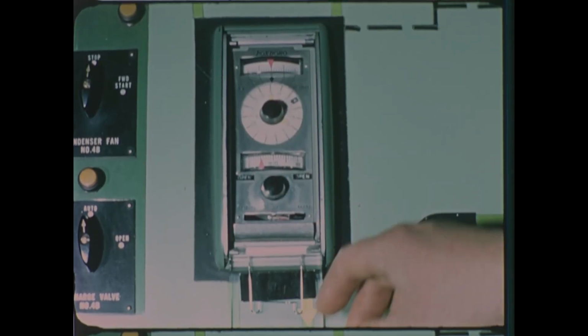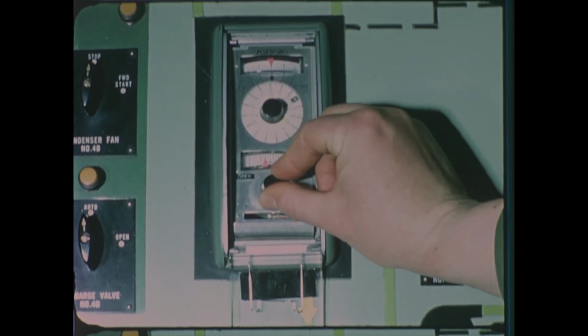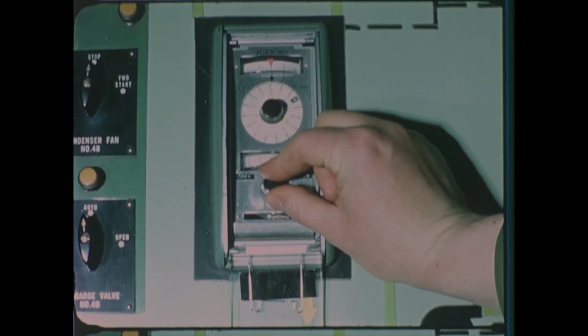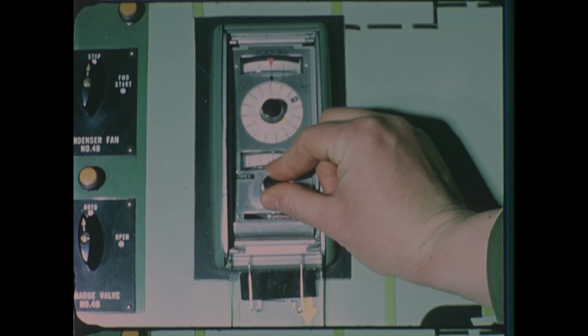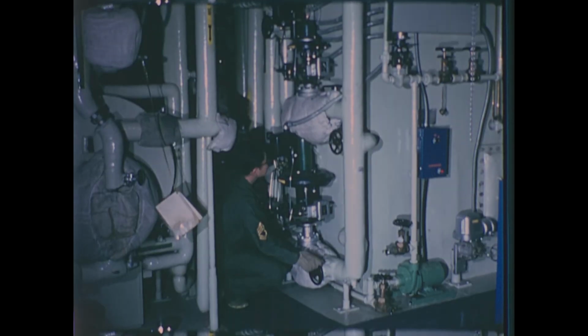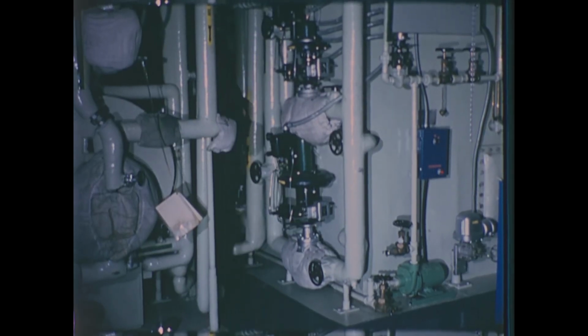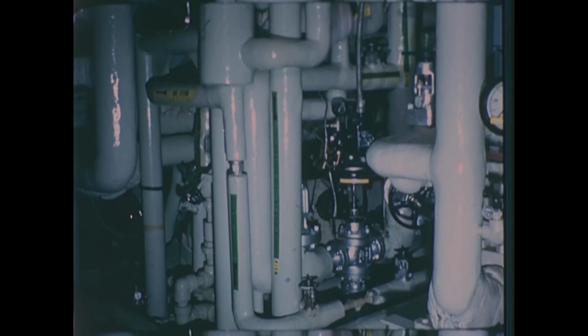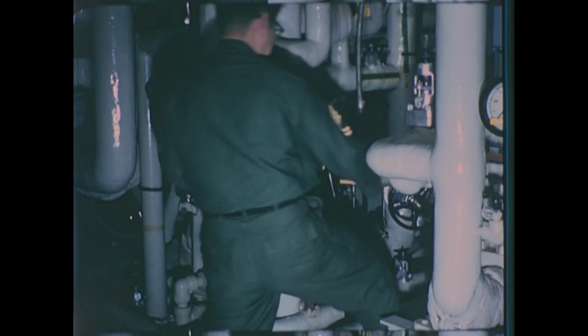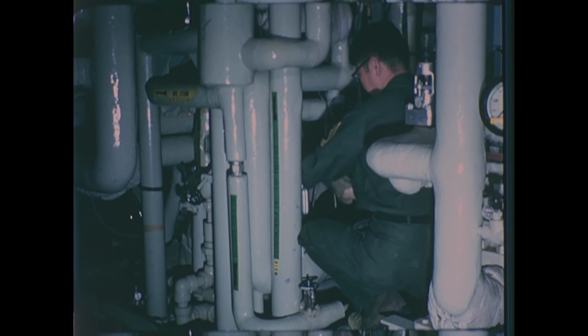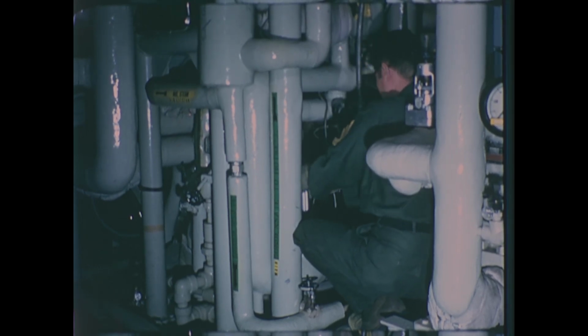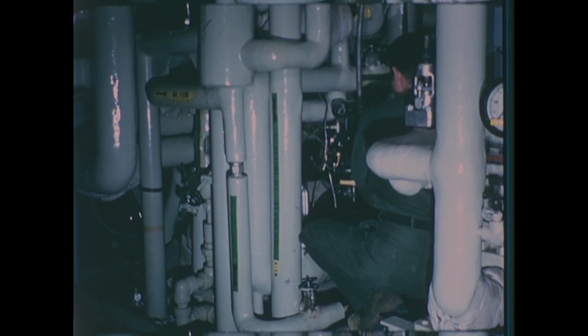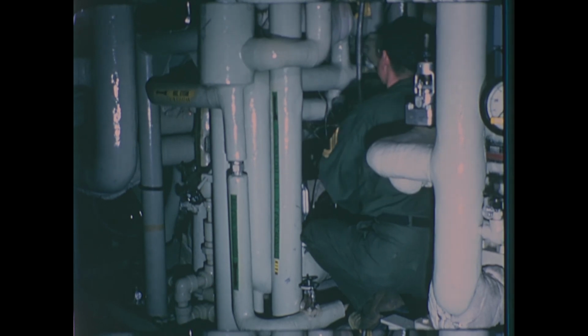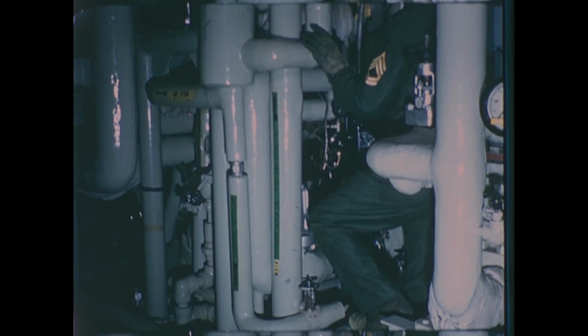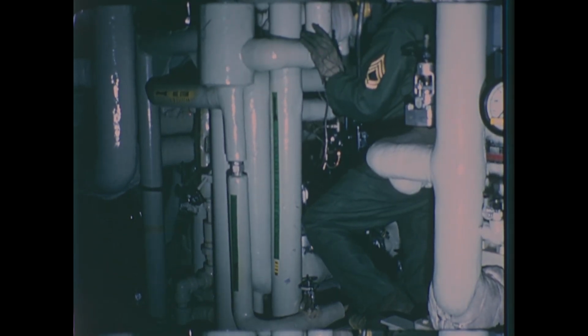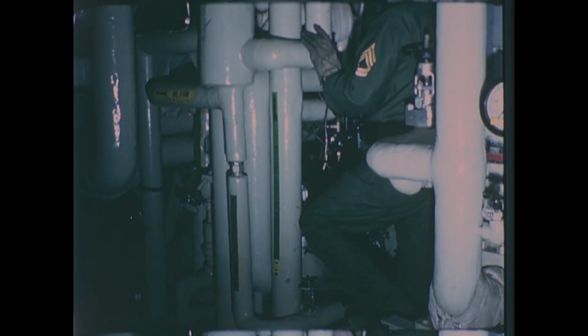Here, the console operator makes sure the control system is operational, while the equipment operator monitors the system check. Next, the equipment operator makes sure the condensate line to the deaerator is properly lined up, and simultaneously checks the operation of the controller. This completes the major steps in lining up the condensate system.